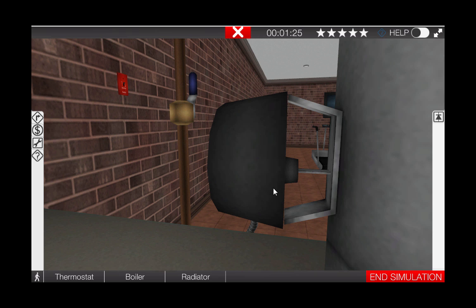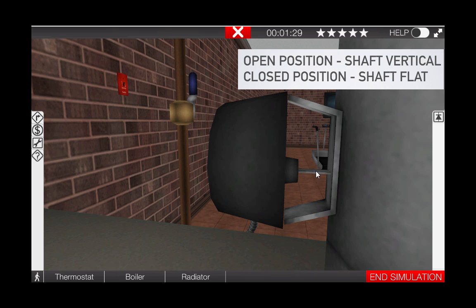To verify if the damper is open, we can simply look at the shaft on the damper. In the open position the shaft should be vertical. As we can see here it's not. The shaft is flat indicating that the damper is closed. This will not allow for burner operation.